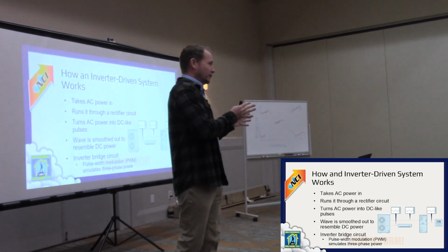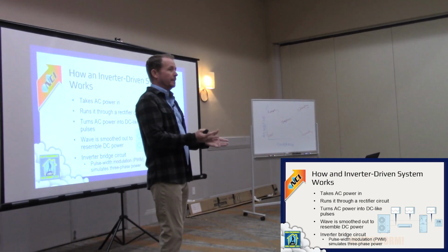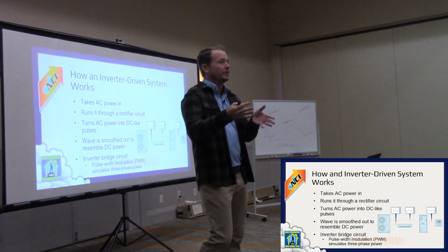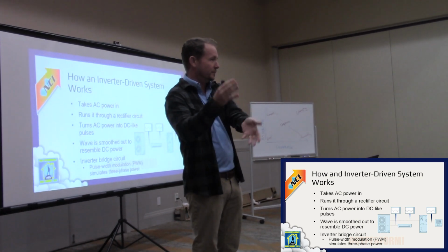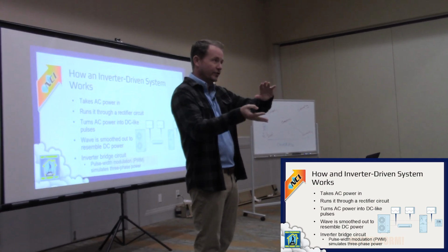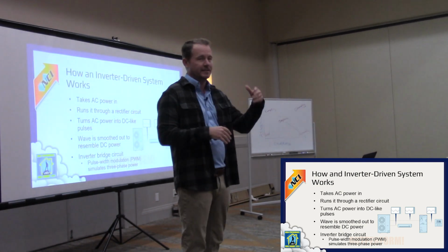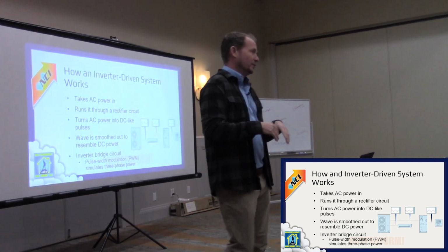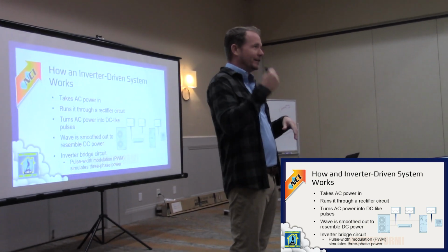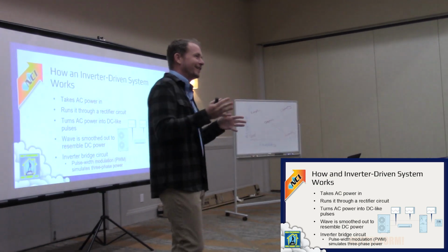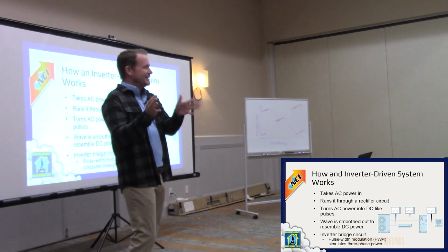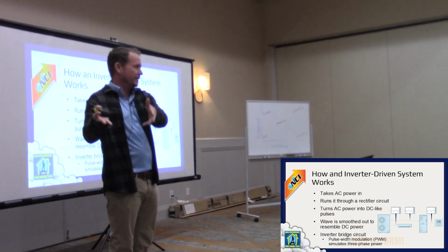With those external variable frequency drives, what they're trying to do is take a motor designed for alternating current and spin it at different speeds. You're actually changing the frequency away from 60 hertz or 50 hertz if you're in one of those other countries. This is America, 60 hertz over here, where you're trying to take that 60 hertz and change it in order to spin things at different speeds.